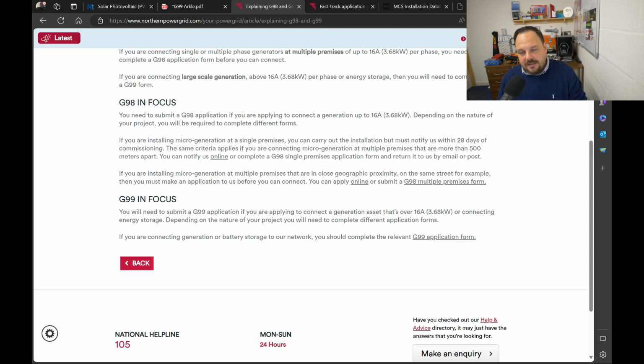Generally speaking now, when people are going for combined battery storage and solar PV systems, you're in G99 territory by default anyway, and most people want solar PV arrays, if they've got the roof space, above 3.68 kilowatts now anyway. So generally speaking, we're doing G99s, and the process for that is you fill the form in to notify the DNO that you want to connect to their equipment.